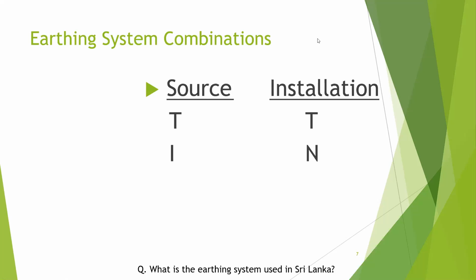The first one is you can have the source connected to earth and the installation connected to earth. So this is called TT. The second one is you can have the source connected directly to earth and the installation not earthed. You are connecting the installation enclosures to neutral. The third one is you are keeping the source isolated and the installation connected to earth. And then we can have a fourth combination, which is IN. But this is actually not an earthing system. To be an earthing system, you should connect at least one side to the earth.